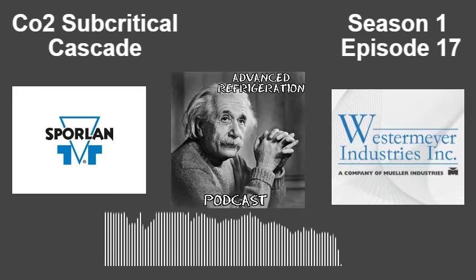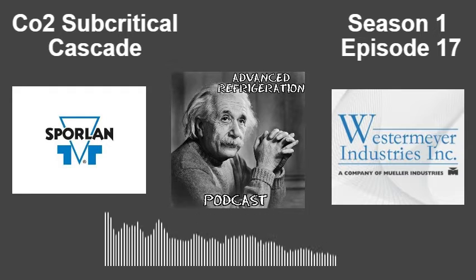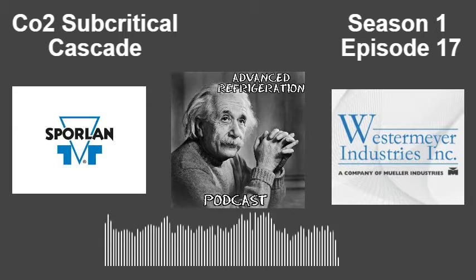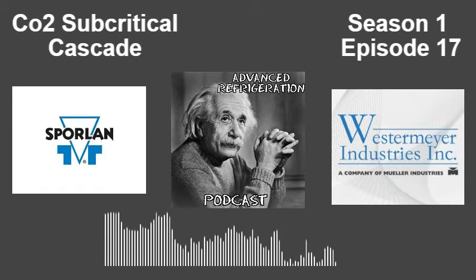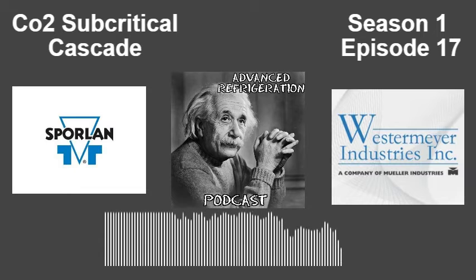So what happens is once the CO2 goes into a de-superheating coil, whether it be controlled with a fan or with a three-way valve, some sort of way to basically bring the temperature down to whatever it was designed for. Most of these systems are designed for the heat exchangers to receive approximately 95-degree CO2. You're still ranging anywhere from 440 to 460 psi on the CO2 side for the discharge of your compressors. But that pressure is going to go up based off of the DX side of the heat exchanger on the medium temp side.